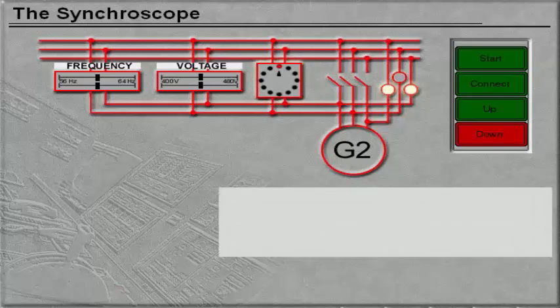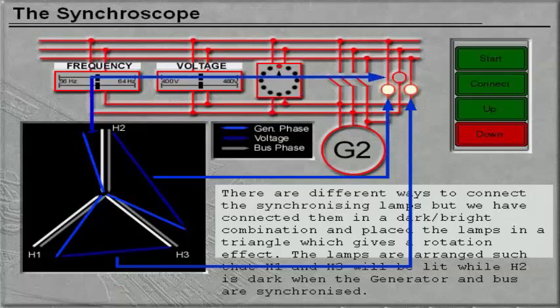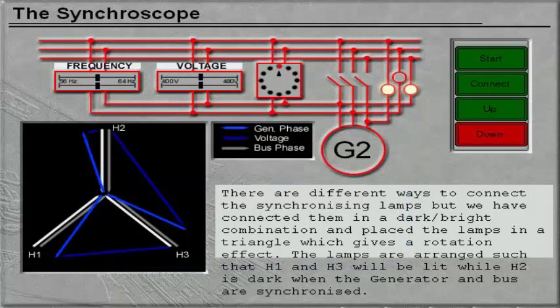There are different ways of connecting the synchronizing lamps, but we have connected them in a dark-bright combination and placed the lamps in a triangle which gives a rotation effect. The lamps are arranged so that H1 and H3 will be lit while H2 is dark when the generator and bus are synchronized.